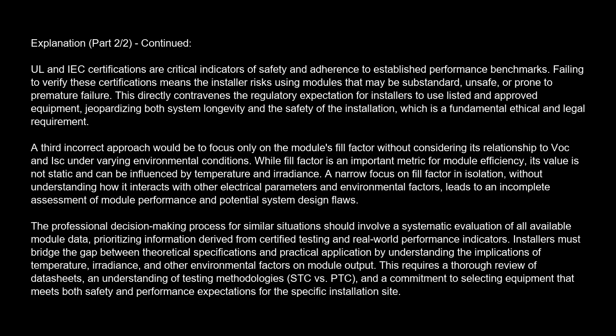A third incorrect approach would be to focus only on the module's fill factor without considering its relationship to VOC and ISC under varying environmental conditions. While fill factor is an important metric for module efficiency, its value is not static and can be influenced by temperature and irradiance. Narrow focus on fill factor in isolation, without understanding how it interacts with other electrical parameters and environmental factors, leads to an incomplete assessment of module performance and potential system design flaws.